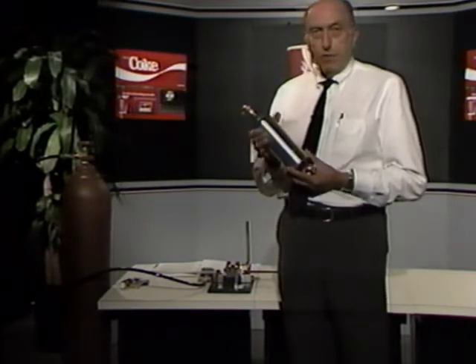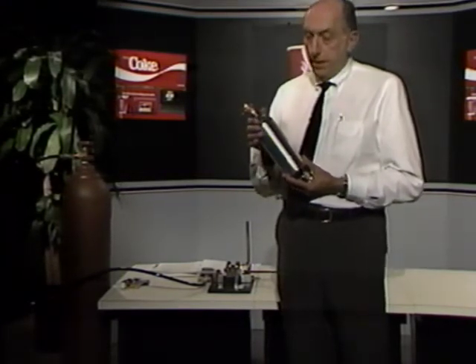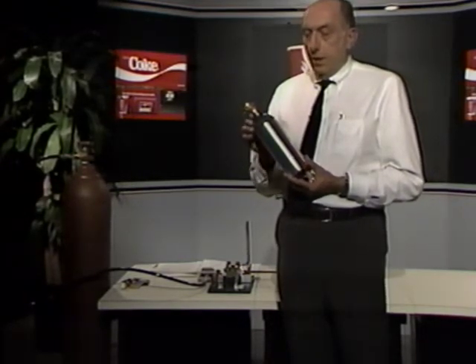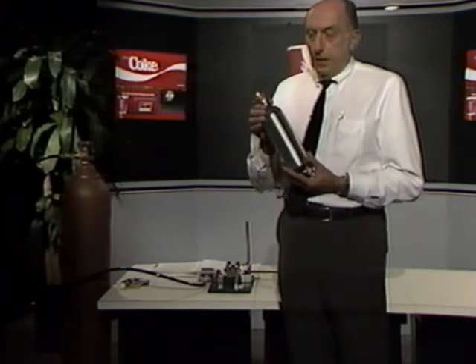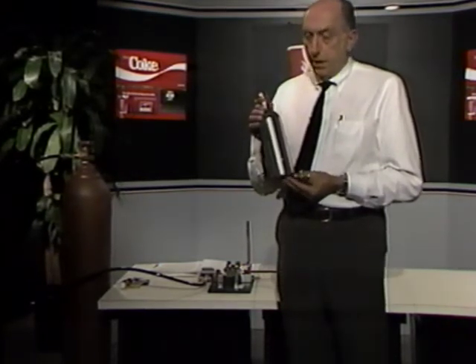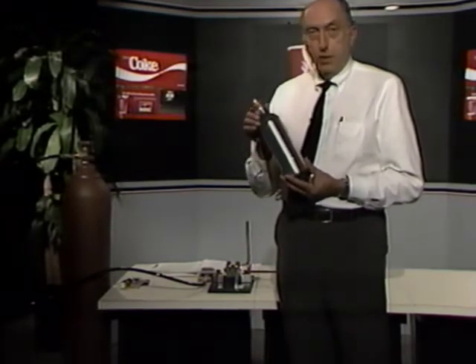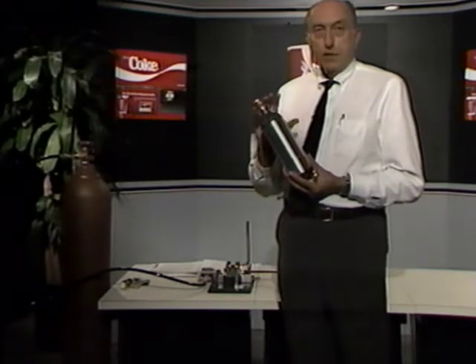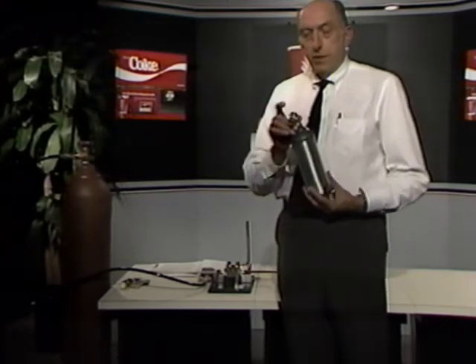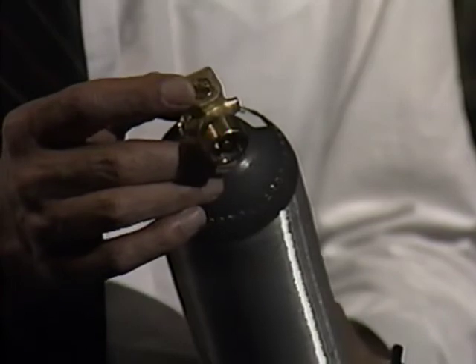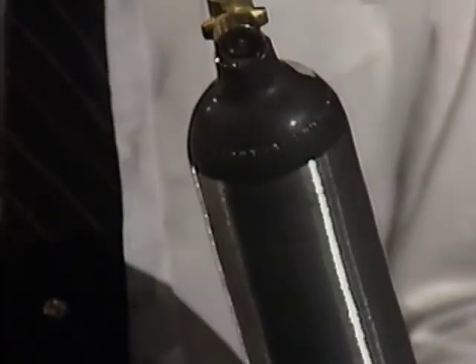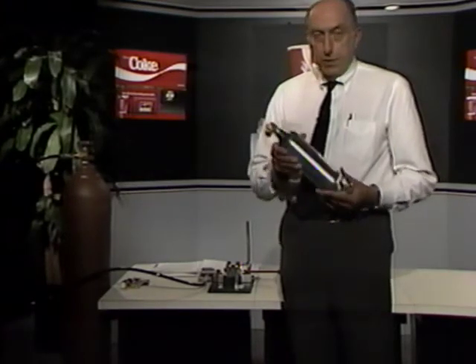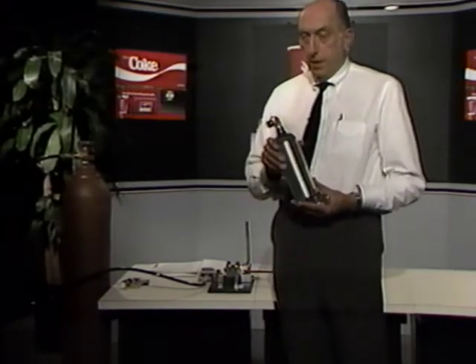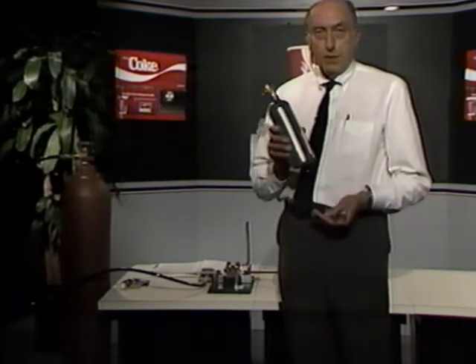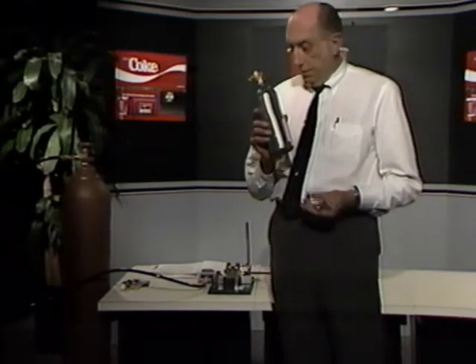And liquid CO2, like water or many other liquids, expands when it's warmed up. So if this cylinder is filled full with liquid, the minute that the temperature rises, that liquid is going to expand and there's no place for it to go. So the pressure becomes very excessive because of expansion of liquid in the cylinder. And for that reason, there's a burst disc in the top of the cylinder that's set to burst at 3,000 pounds pressure. And we've had instances where people weren't paying attention and filled it too long, and they find when they put the cylinder in their truck and it warms up, it bursts the disc. And the only reason this disc will burst is because the cylinder has more than 3 pounds, 5 ounces total weight.